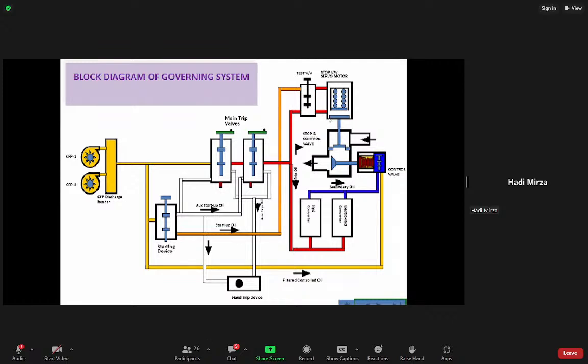And then trip oil goes from the bottom of the above piston of the servo motor, and then this cup will be compressed against this spring and come to sit around here. This is called the cup and this is called the saucer. For a layman, you can understand it like this. When the trip oil comes above the piston for resetting the stop valve, this spring will be compressed first and become a complete single assembly in the servo motor.